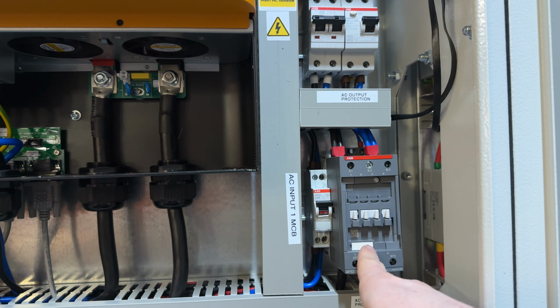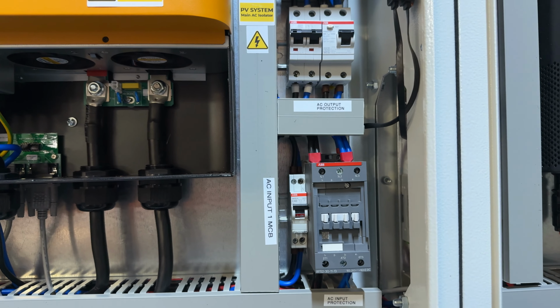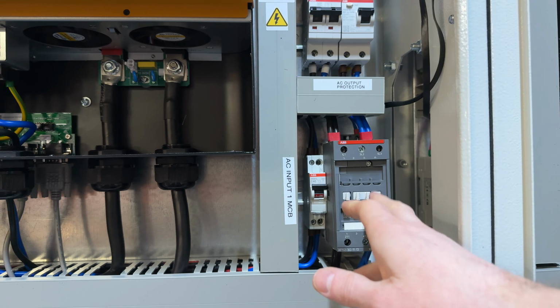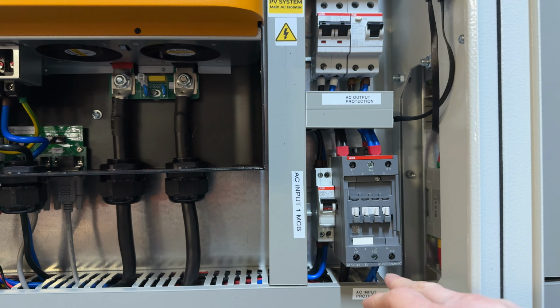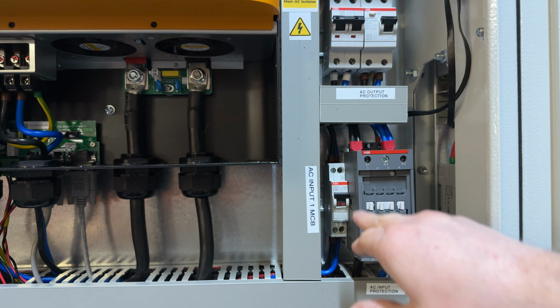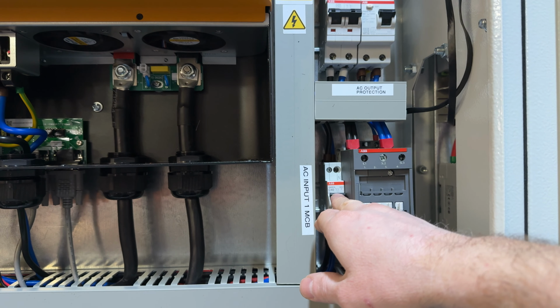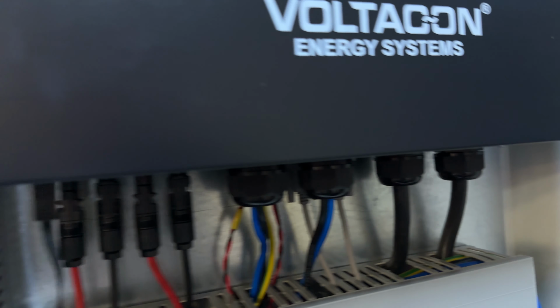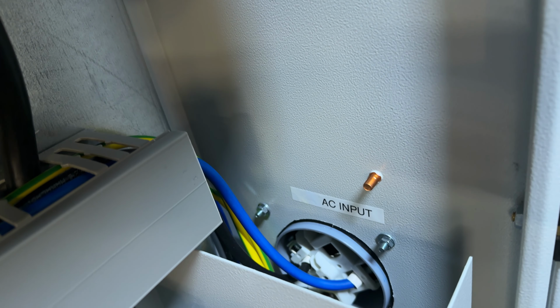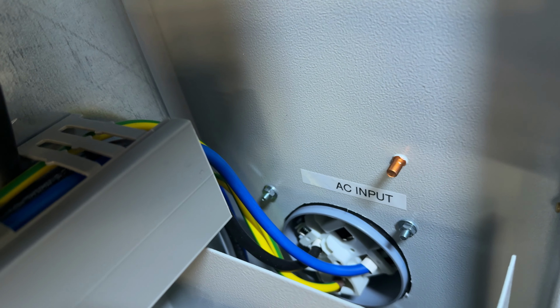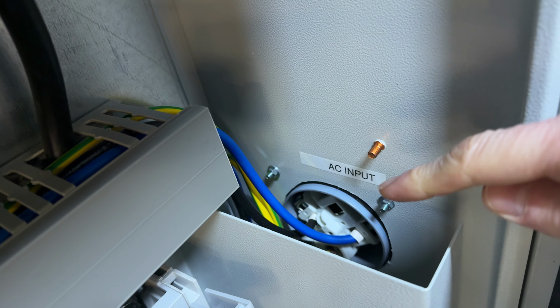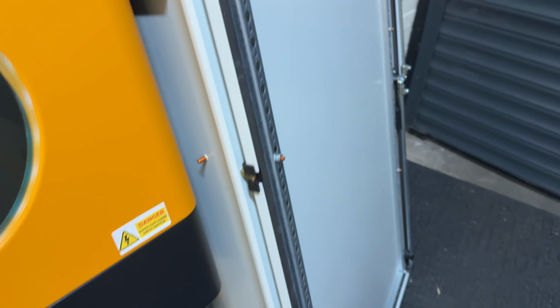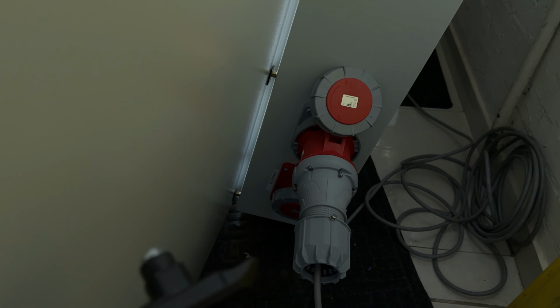This is the input to the system. If you have a backup generator or a grid connection, this is controlled by this relay. That's the AC input MCB, and here are the AC input terminals. They are pre-wired in single phase mode. So the top socket is connected to the grid and nowhere else. You shouldn't connect any other loads to the top socket.